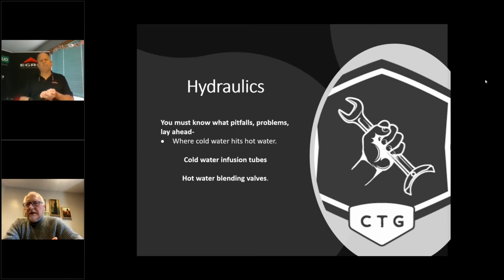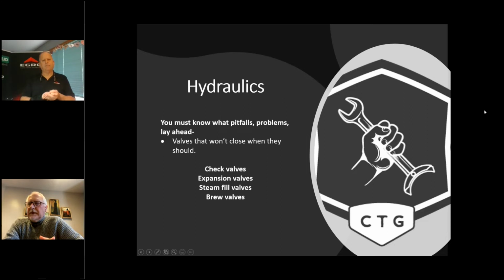Copper can actually corrode from the inside. It's not usually a problem with espresso machines if they're just running water softeners and filtration systems, but if you try to run a straight RO and you don't have any bypass, or you don't have a... what is the filter for feeding dissolved solids back into the water? Mineral addition. Polishing. Yeah, thank you. Then you can have other issues with the machine. The problem with that is, you can remove calcium, but you can't add back copper. So might be dangerous. Okay, Don, back to you.